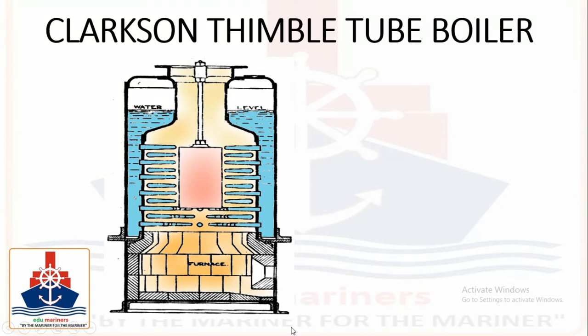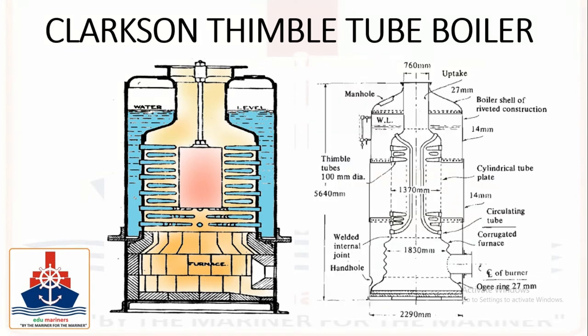These boilers will operate for long periods without internal cleaning. However, if an undue amount of scale forms inside the thimble tubes it is very difficult to remove. So a reasonable quality of feed water should be provided. This type of boiler shown on screen is oil-fired.